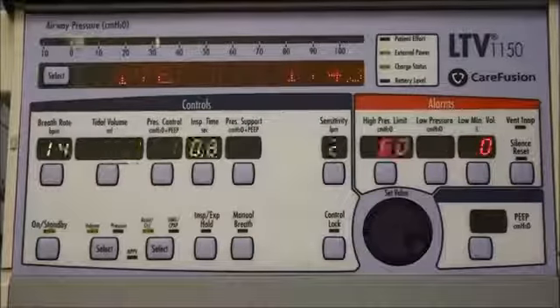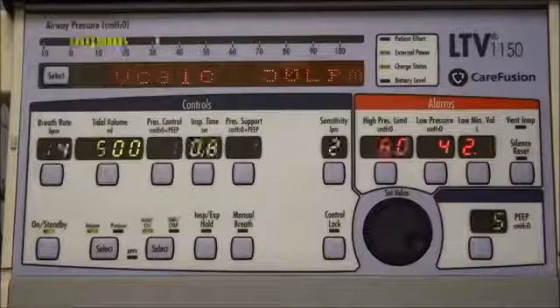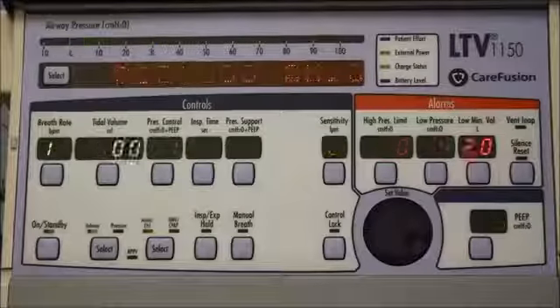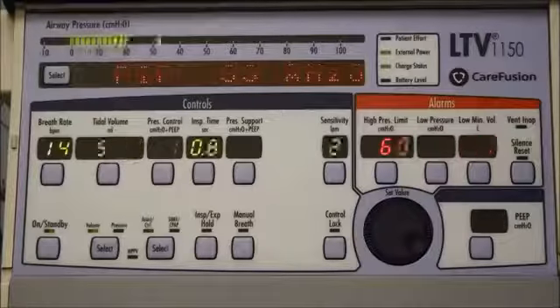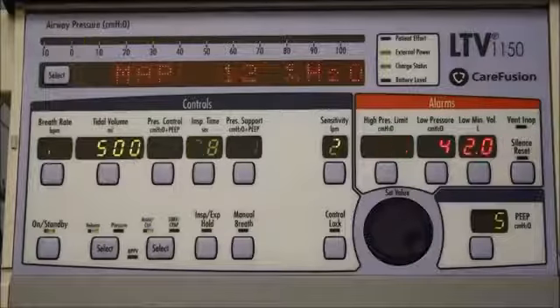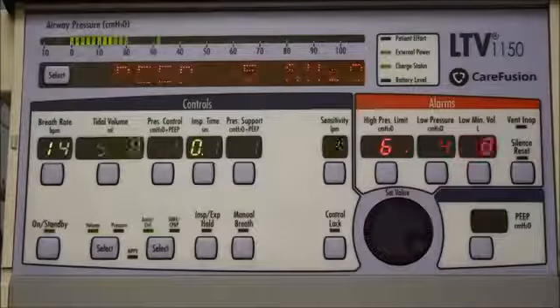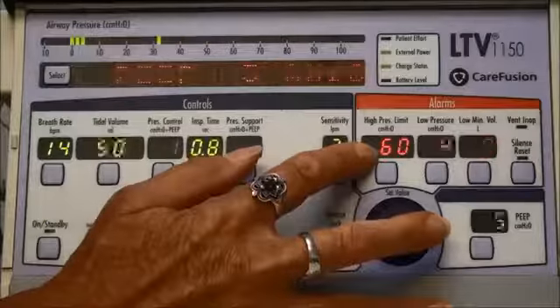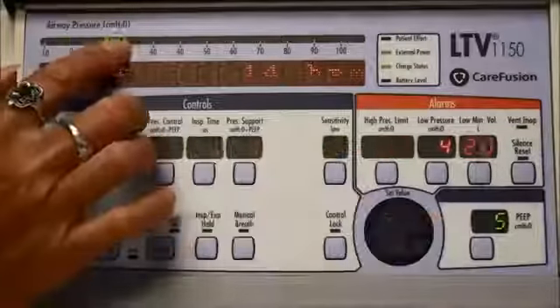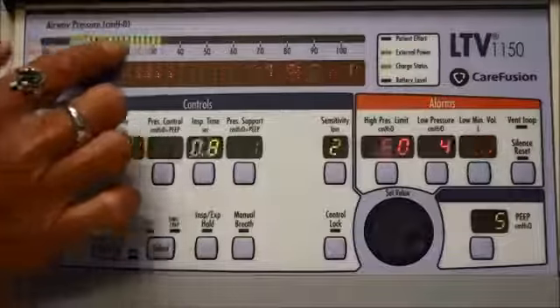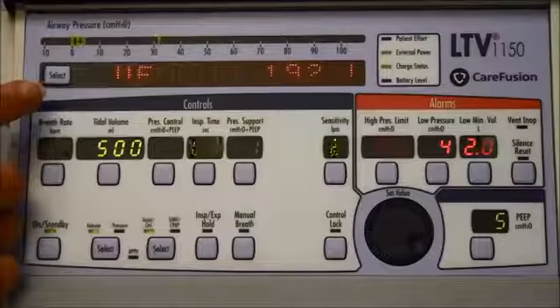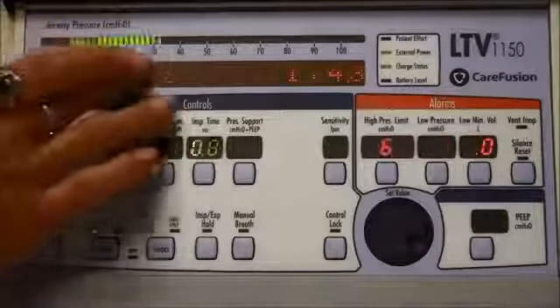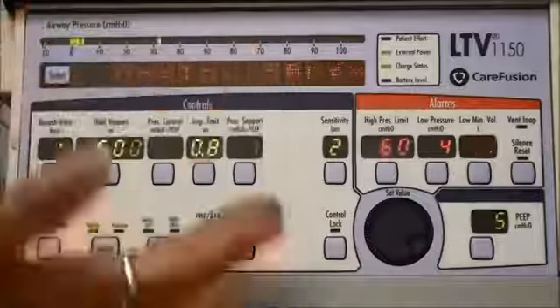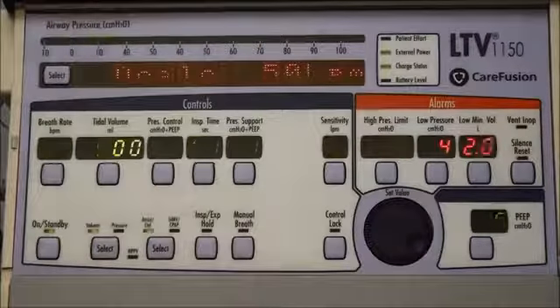So a high pressure alarm can be caused by any sort of obstruction in the tubing, water in the tubing, if a patient needs to be suctioned, if a patient's coughing, or even sometimes if a patient is speaking. And what would happen is you would see that we have the high pressure set right now at 60. And you can see that the pressures that our pretend patient is giving us is running a little over 30. So if something occurred to make this pressure go up above 60, you would get an alarm. And I'm going to demonstrate that.